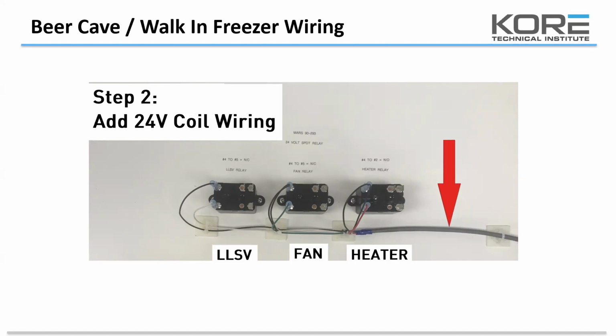So in the older stores with EMS installation, be aware that you do have either the neutral being switched or you do have one of the 208 legs being switched. In this particular picture, as you take a look, the red wire will always go to the heater relay. The green wire will always go to the fan relay, and the white wire will always go to the liquid line solenoid valve.